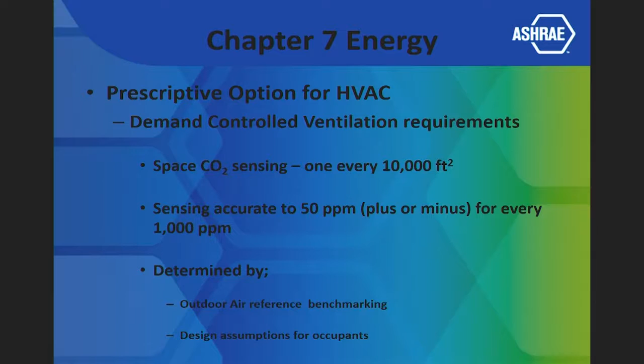Demand control ventilation. People know what demand control ventilation is in a building? It's basically throttling and controlling the amount of fresh air I'm going to bring into the space, because what they originally set up for how much air you need, like for this room, for example, all the diffusers, I'm bringing in air so you feel comfortable. Well, part of that process is how much fresh air from the outside am I bringing in? Well, the code says, look at all the seats. That represents a body. I'm up here, that's a body. There's people walking around, those are bodies. They all have to be part of the original design intent for how much fresh air you need. Are we going to be here from the start when the doors open to when we leave? Everybody?